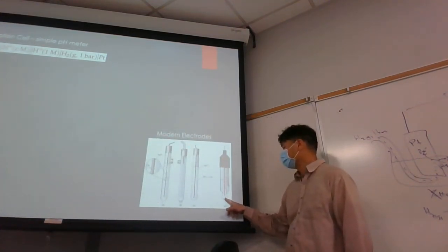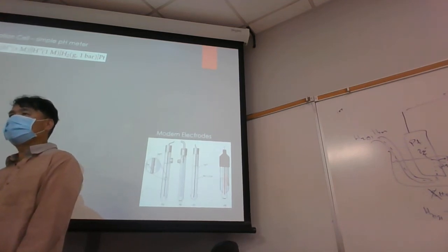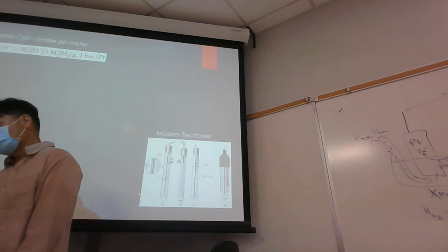But one thing with these glass bulbs, you don't want them to dry out. It's a gel on the surface, and if the gel dries out, the response gets very slow. And so these pH meters can be very sluggish, especially if they've been dry for some period of time. Then you try to record a pH, and it takes hours for it to get there. So the electrodes have to be well conditioned. That's why I personally prefer a different type of pH meter.